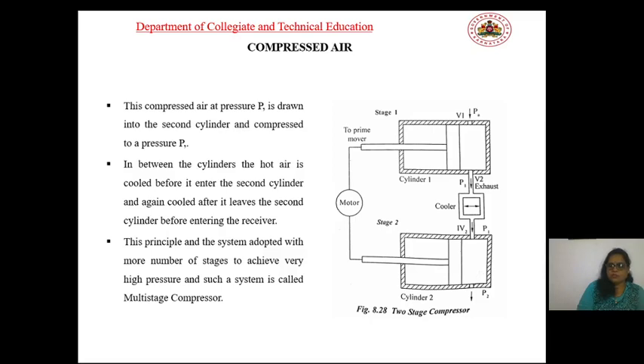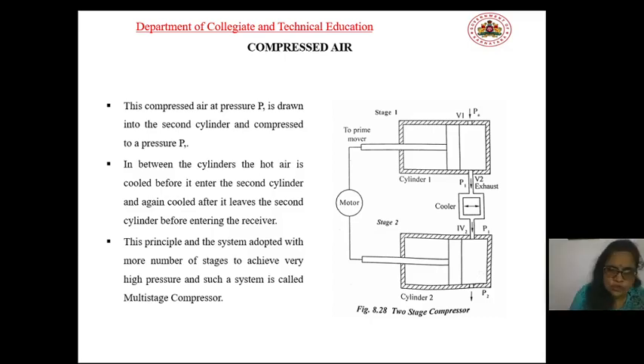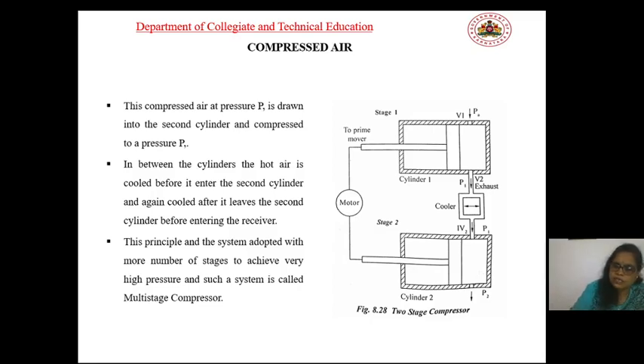The compressed air at pressure P1 is drawn into the second cylinder and compressed to pressure P2. In between the cylinders, the hot air is cooled before entering the second cylinder, because as pressure increases, temperature also increases and could damage parts. This working principle can be extended to more stages to achieve very high pressures — such a system is called a multistage air compressor.